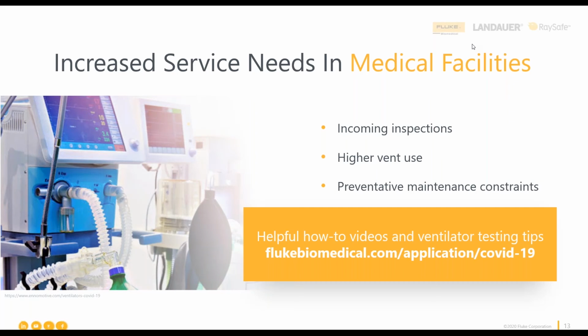The field service teams needed to increase. I hadn't heard anything about new installation activity from the medical device manufacturer's field service, but it certainly increased the need. And the more use hours per ventilator, the use hours are often a determinant of when scheduled maintenance needs to be done, as opposed to a calendar schedule. So all of that tend to put a big increase on the requirement and the demand for doing testing beyond just what you normally might have done.